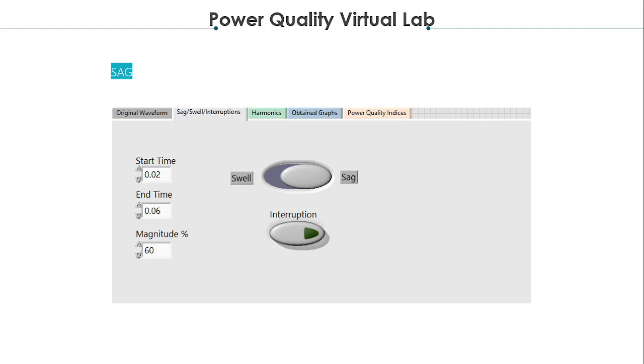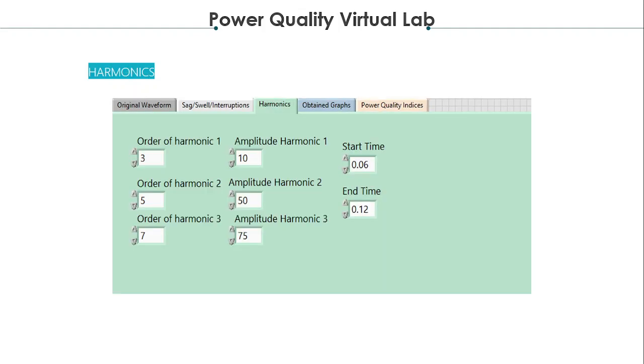In addition to the sag created, the signal is distorted by three harmonic components of order 3, 5, and 7 with magnitudes of 10 volt, 50 volt, and 75 volt respectively, as shown in this UI screen. These harmonics interfere in the signal between 0.06 seconds and 0.12 seconds. Up to 50 harmonics can appear in a system. However, only 3 harmonics can be added in this virtual tool, as its main purpose is to learn and investigate the basics and measures of power quality.